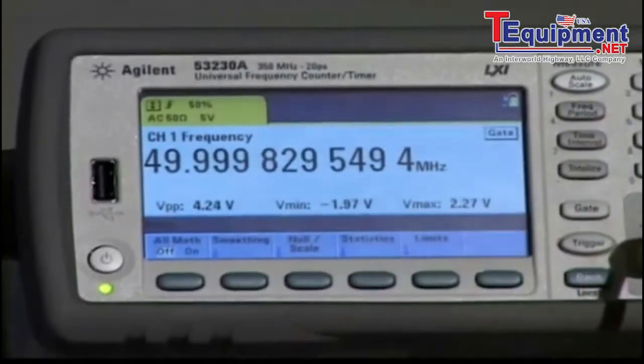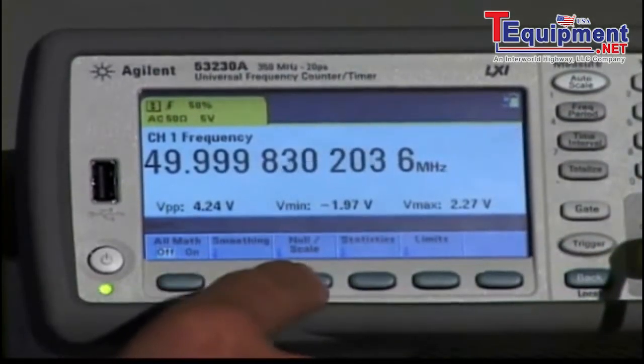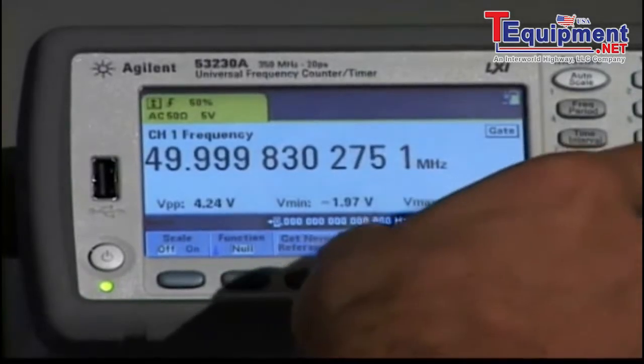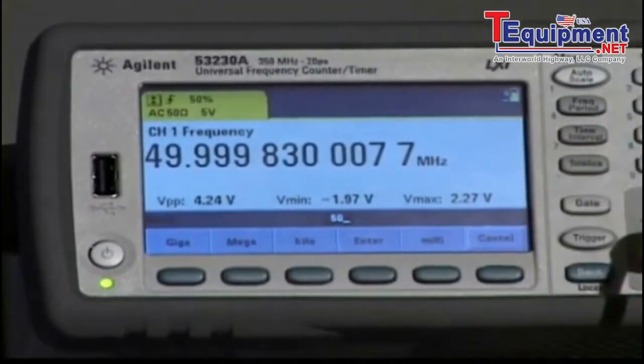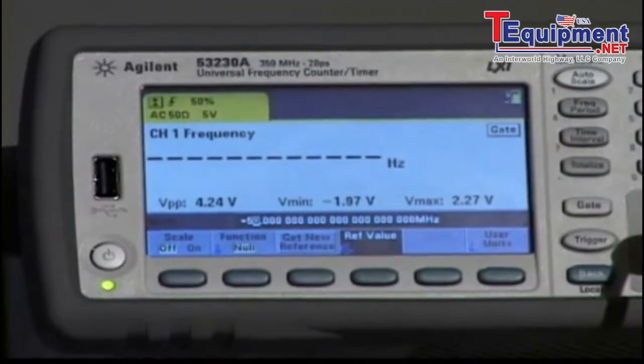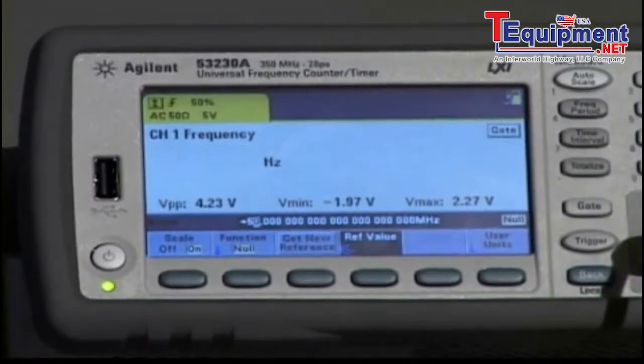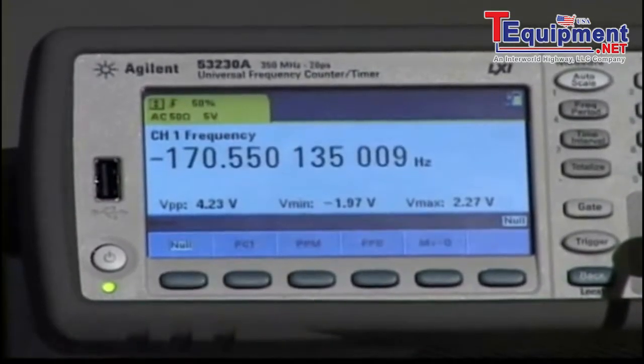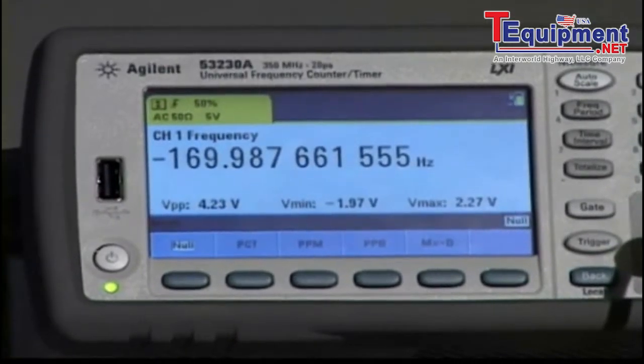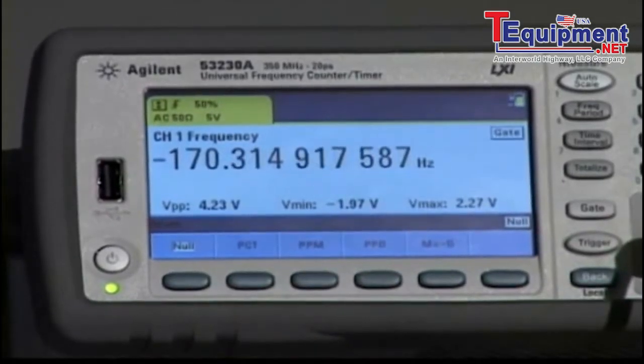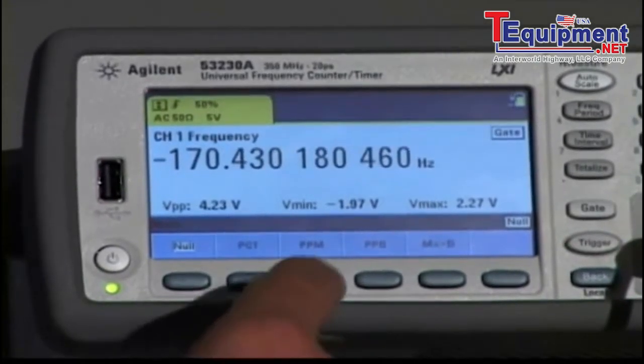So I can go math, I can go null scale, then I'm going to enter in 50 megahertz because that's my reference value. Then I'm going to turn my scaling feature on, and I can show null, which is just hertz. I can show percentage, I can show parts per million, I can show parts per billion, and then I can do a custom one. I'm going to show parts per million.